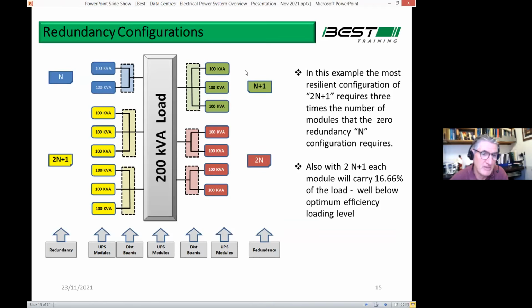This diagram I mentioned about resilience, it just shows typically here, if you look top left, you have a load of 200 kVA, as you see in the center. So the 200 kVA represents, say, a data hall with a 200 kVA load, which is not realistic. It would be 2000 kVA maybe. And you decide to use a 100 kVA module.